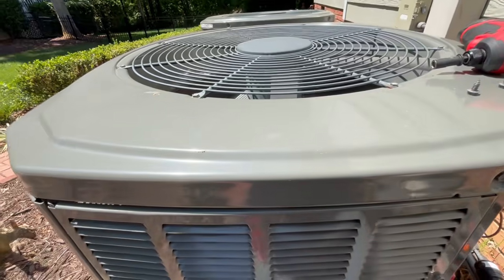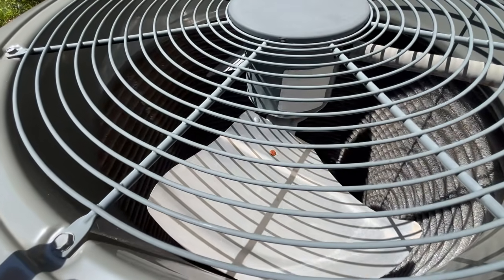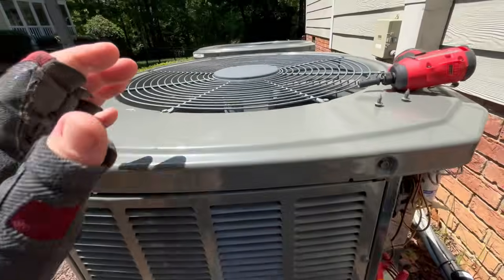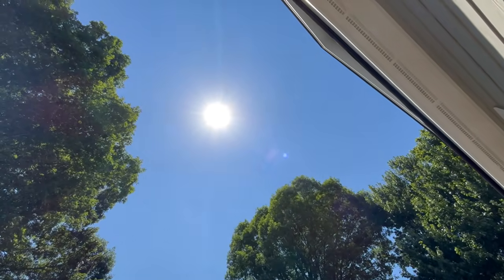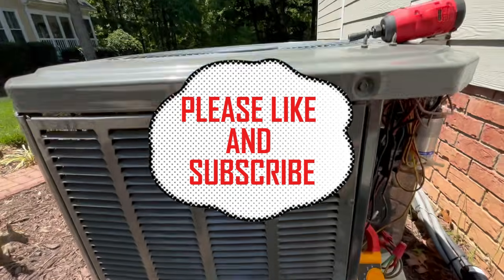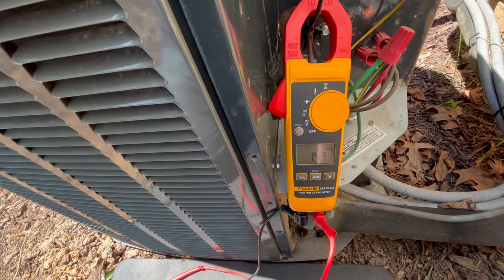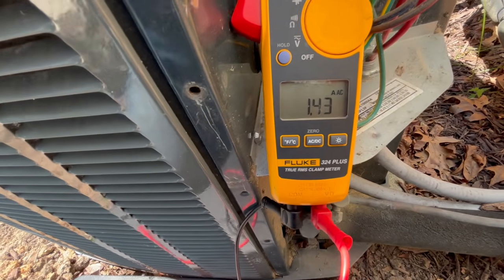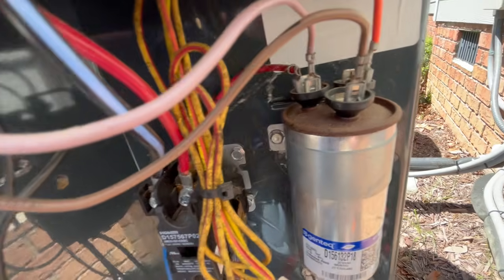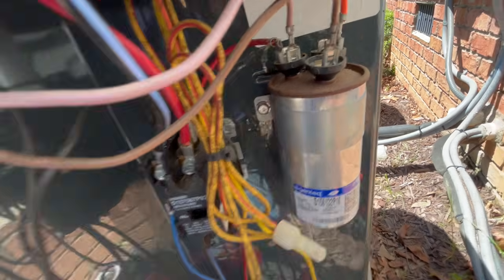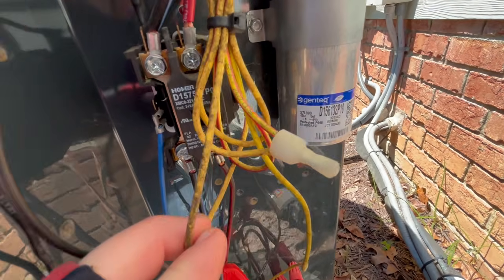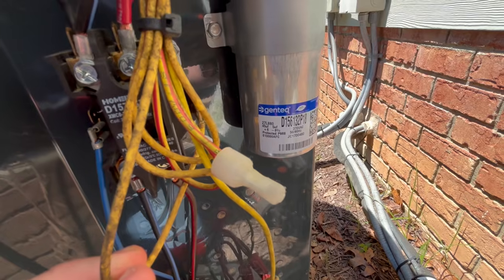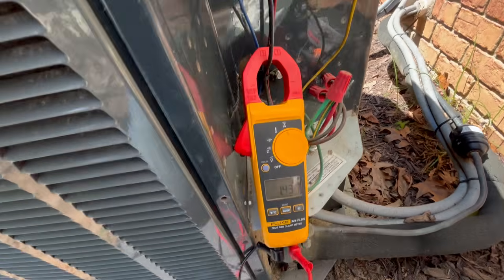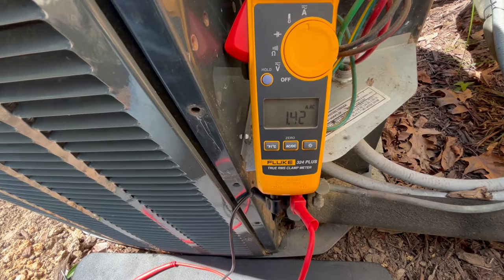Guys, we've got an upper air conditioner not working on this house. It's 85 upstairs and it is 95 outside. I'm waiting for it, but it's going to be a death buzz because of another bad capacitor. And that one is also a 45/5, just like the other one was. Maybe they made a bad batch of those, I don't know. This unit is 6 years old.